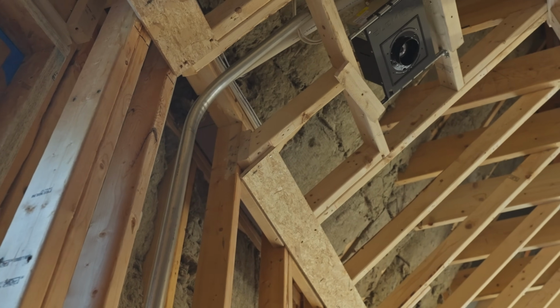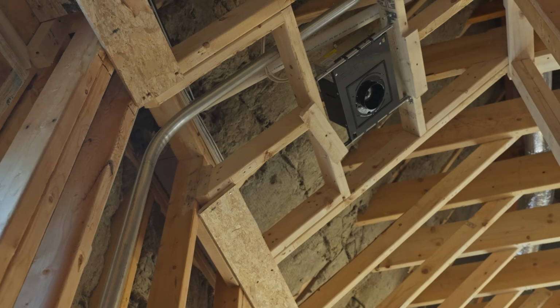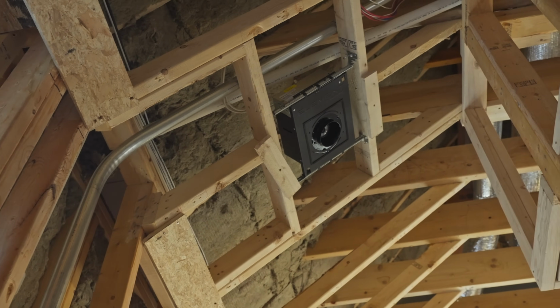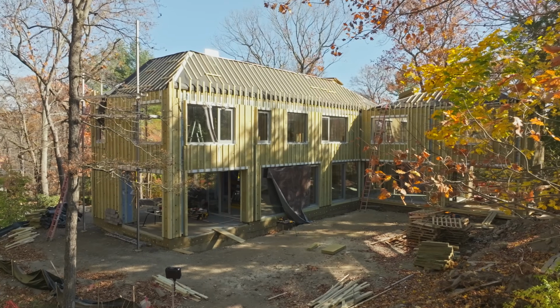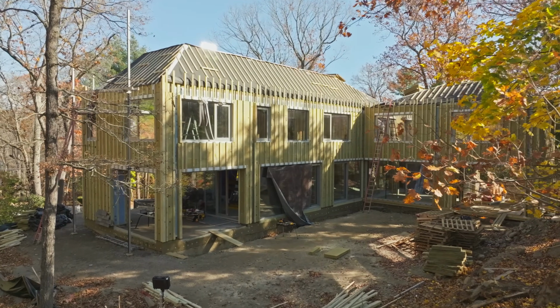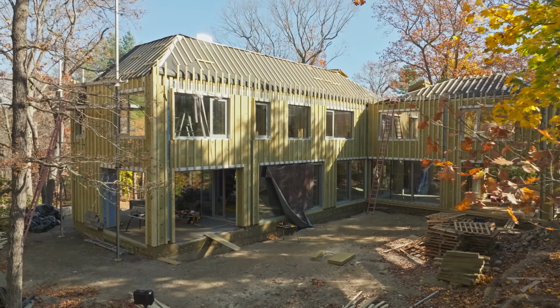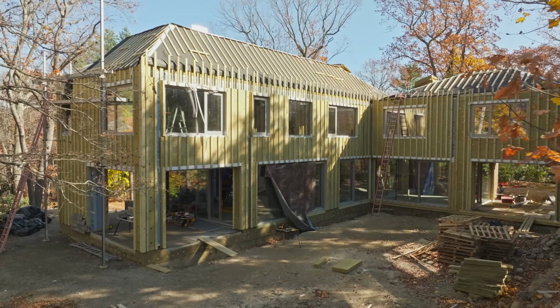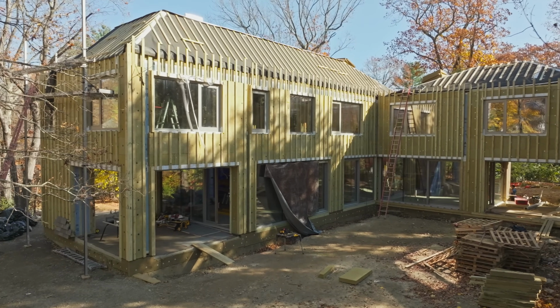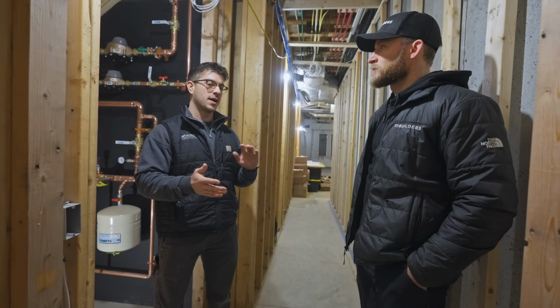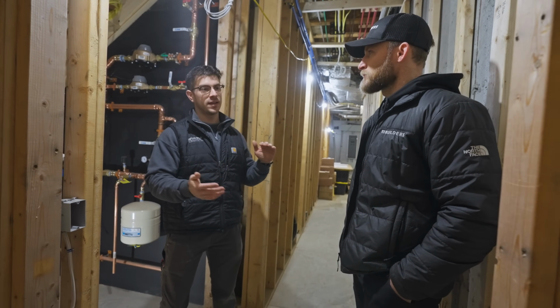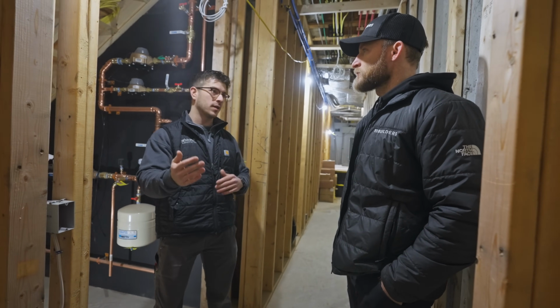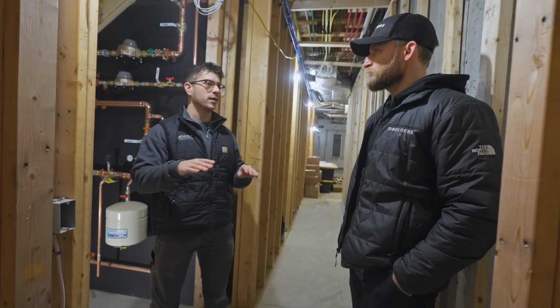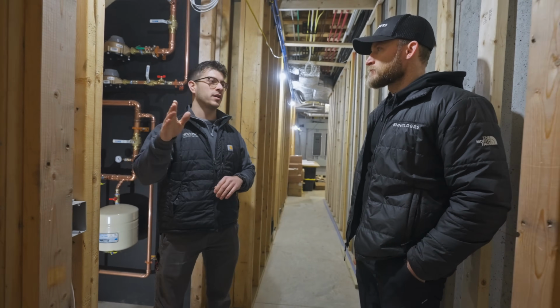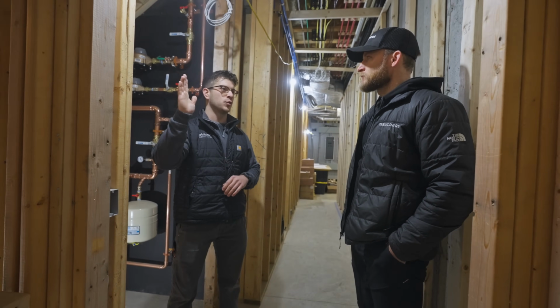So EMT—what does that stand for? Electrical metallic tubing. The challenge with prepping for solar and running a conduit up to the roof is how many times it bends, is that right? Correct. We can't have anything more than 360 degrees of bends before we hit a pull point, which would require a can, and that can would need access—so then you have access panels in the walls, essentially stuff you don't want. We found a nice clean chase where we could go up, and I believe we only have 220 degrees of bends right now.